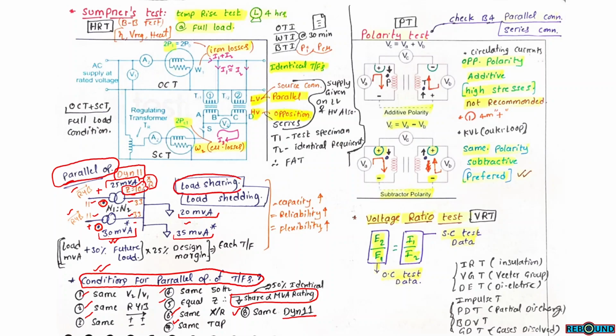Coming to load sharing, now the total load is 55 MVA and the total transformer capacity is also 55 MVA. So the 25 MVA transformer will feed 25 MVA load, and the 30 MVA transformer will feed 30 MVA load. Now if we assume that the 35 MVA load is disconnected from this bus, then the total load on the bus is only 20 MVA.